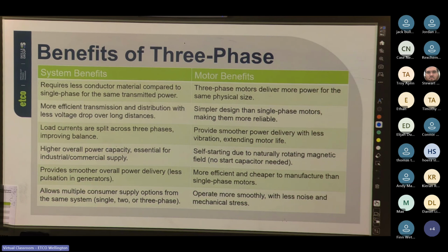The main advantage is capacity. So, for example, homes with high demand appliances like EV chargers, large heat pumps, spa pools, multiple ovens, induction ovens, may need more than a single 230-volt supply can deliver. Taking two phases provides extra supply without needing the full expense and infrastructure of a three-phase installation.